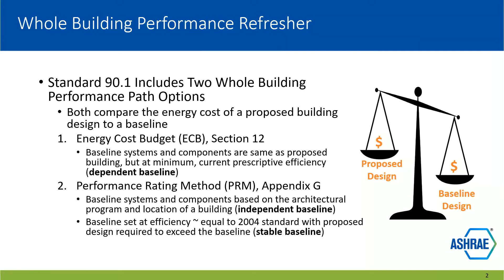Also, unlike ECB, the efficiency values in the Appendix G baseline are set at a level approximately equal to the efficiency of the 2004 version of Standard 90.1 instead of the current version of the standard. Because of that, the proposed building energy cost needs to be substantially lower than the baseline energy cost in order for the building to comply under Appendix G. As each new edition of the standard improves and the baseline remains stable at the level of the 2004 standard, the compliance margin between the proposed energy cost and the baseline energy cost increases.